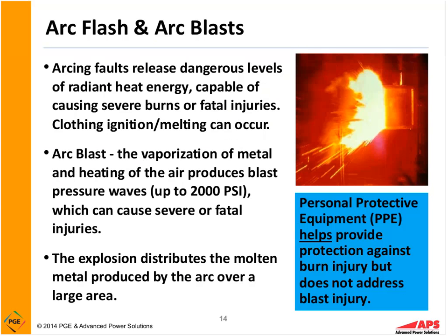So in a nutshell, when we have this blast pressure wave, not only does it spread the arc over a wide area, but it can also create internal injuries. In other words, if we get hit with this big blast pressure wave, it can cause an internal injury, and that's why we limit how much energy we expose ourselves to. Electrical PPE will help provide protection against the heat, if we properly select it and apply it, but will do nothing to protect against the internal injury from the blast pressure wave.